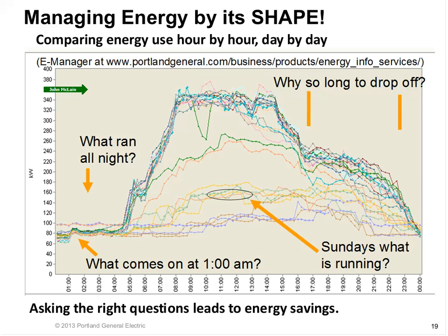So one of the first questions I liked was what comes on at 1 a.m. every night, weekdays, weekends, every single night. I was told by the facilities manager that he kept asking staff, and no one seemed to know what comes bump in the night. It comes on about 1 a.m. and stays on until everybody comes in. And finally, one day, the IT department raised their hand and said, that's the computer backups that run at night. Everybody's computer gets backed up.